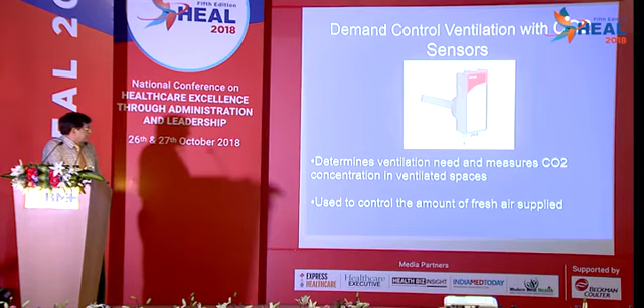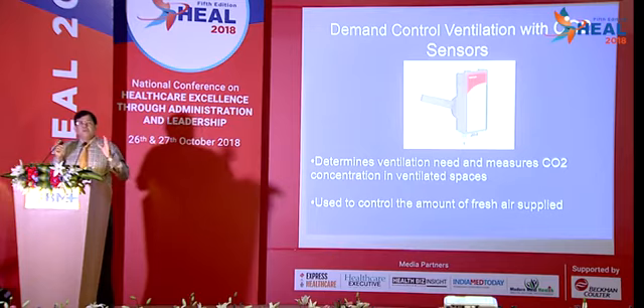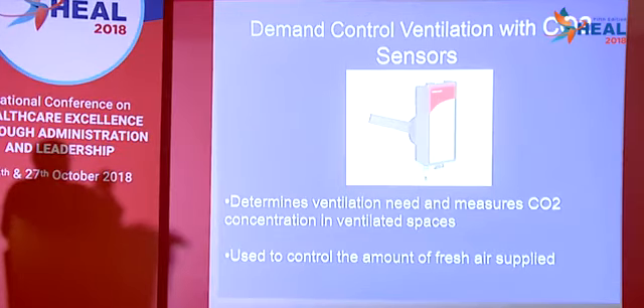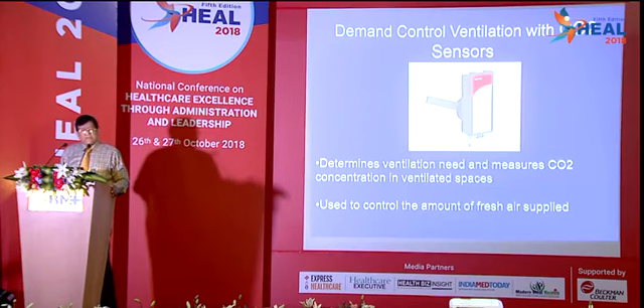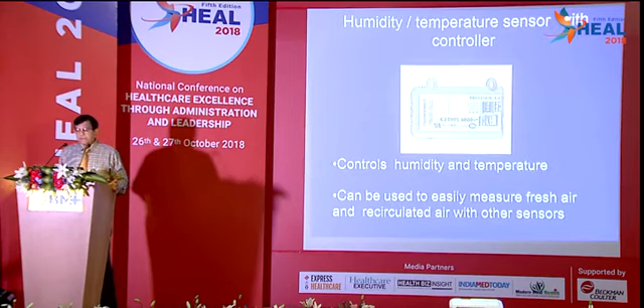We can have CO2 sensors with integrated building management systems, and a CO2 sensor can determine ventilation need and measure CO2 concentration in ventilated spaces. It is used to control the amount of fresh air supplied. How much fresh air you want to supply to your critical care areas, to operation theatre or ICU, can happen with the help of CO2 sensors, which will be a part of the building management system. Or we can have a humidity temperature sensor with a controller to control humidity and temperature while sitting in the office. Temperature and humidity of any operation theatre in a multi-storied building can be controlled by somebody who is sitting in the engineering office.